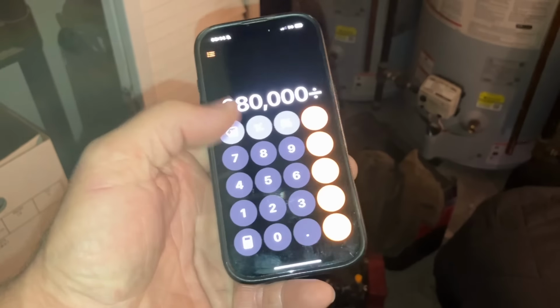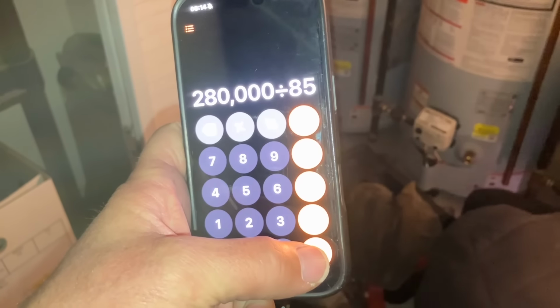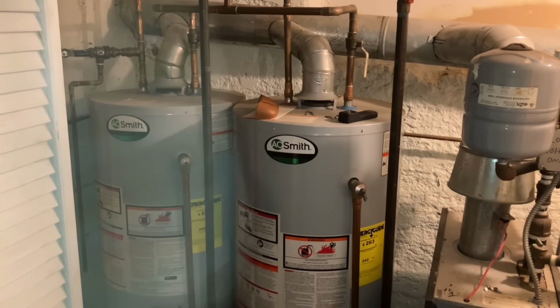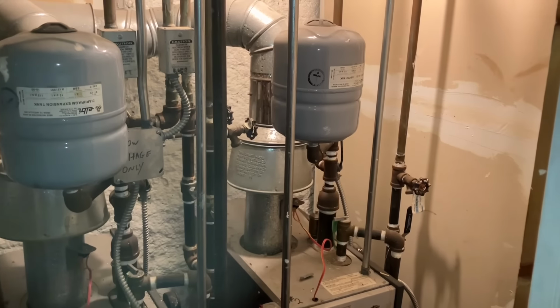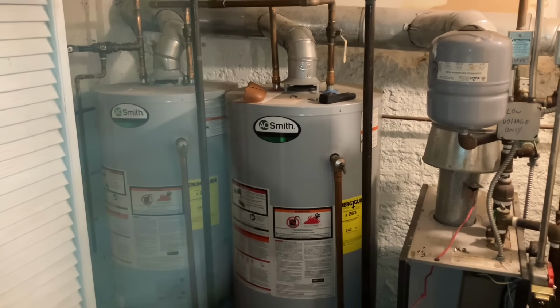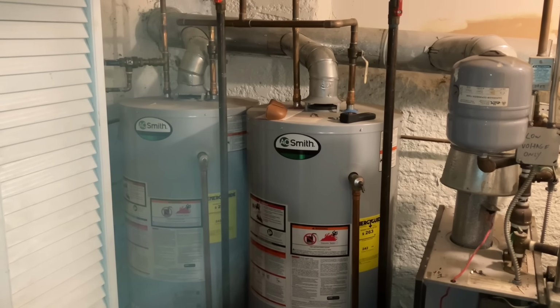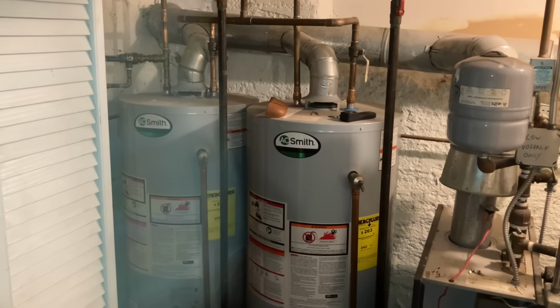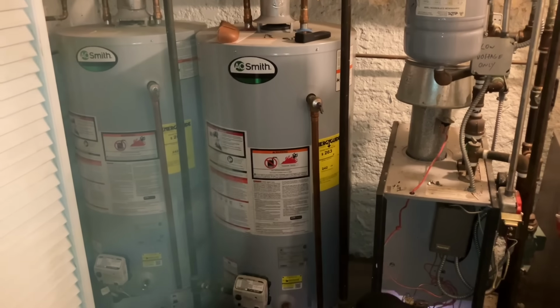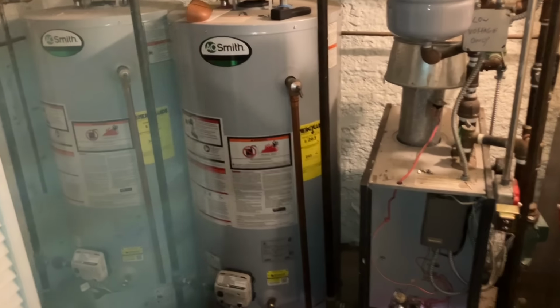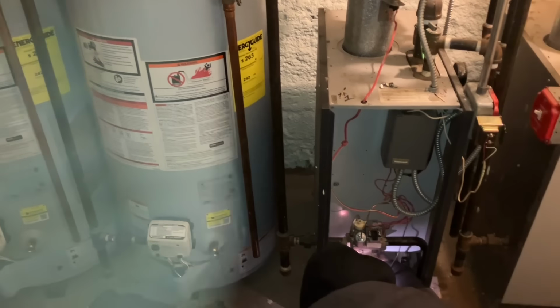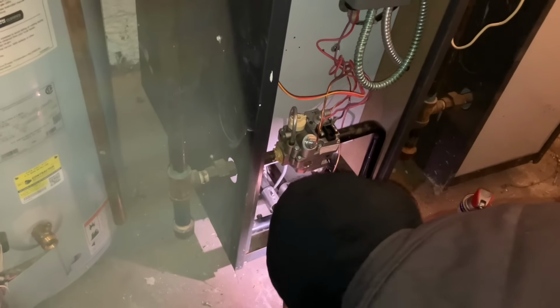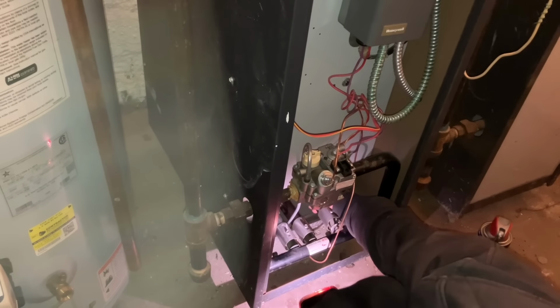So let's figure around 80 to 90 BTUs is 1 candle. Let's do some math. 280,000 divided by, let's do 85 watt candles. Well, you know what I mean. 3,295 candles. So imagine, I don't know, 3,300 candles are burning in this closet, right? What do you think's gonna happen with those candles, folks? You're gonna starve of fuel, of oxygen, sorry. You're gonna be starving for oxygen with 3,300 candles burning in here. Yeah, it's gonna suck in some air through these louvers, but still not good. So that stresses the importance of fresh combustion air for your gas burning equipment. Or it's oil, doesn't really matter. All right, Derek is reinstalling the burners.